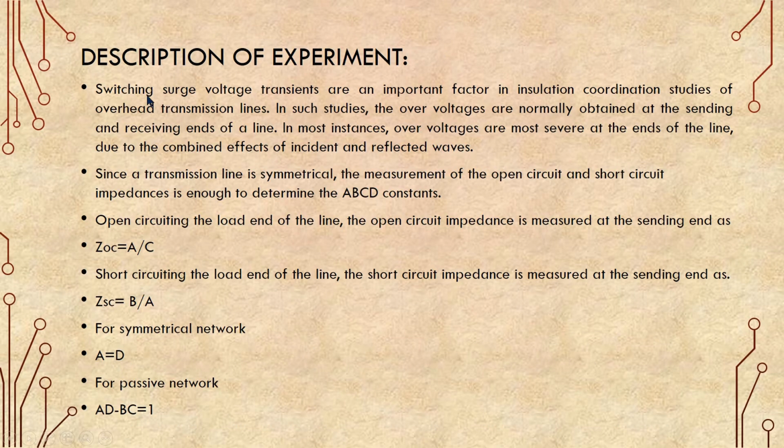Switching surge voltage transients are an important factor in insulation coordination studies of overhead transmission lines. In such studies, overvoltages are normally obtained at the sending and receiving end of the line. In most instances, overvoltages are most severe at the end of the line due to the combined effect of incident and reflected waves.